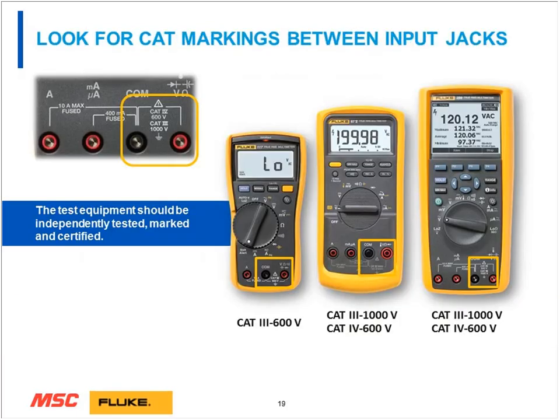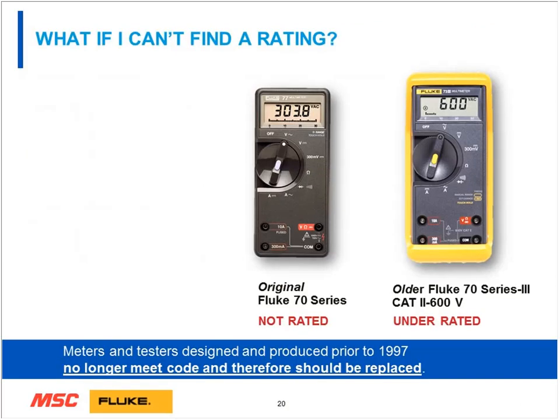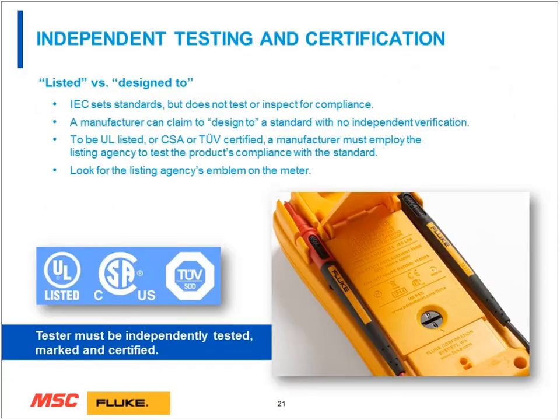Always look for the CAT markings between the input jacks of any instrument. It could be on a scope meter, it could be on any device. And here you'll see where we have Category 3 600 volts. There are some that are dual rated, the Category 3 1000 volts or Category 4 600 volts. What if you can't find the rating? Don't use the instrument. The bottom line is before 1997, we didn't have that rating structure in place, but now we're using circuits, we're using equipment on circuits that have a greater amount of current available.